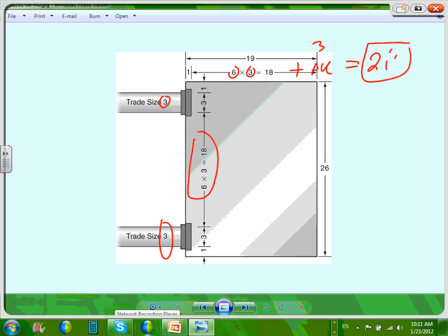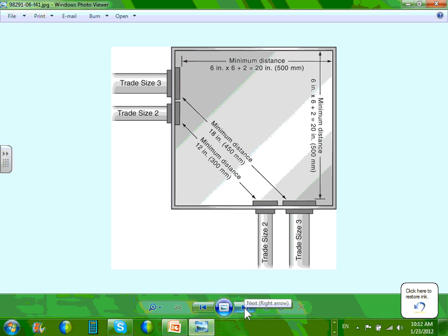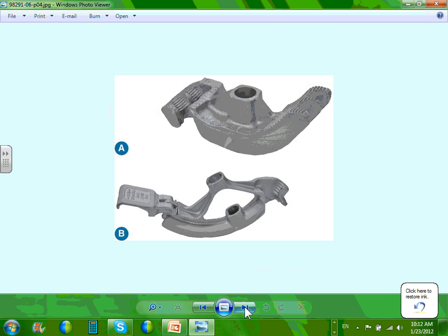Any comments, guys, about the pull box? We're not using a pull box in this project, but really pay attention to the 6 times the largest conduit if it's a U or angle pull, and 8 times the largest conduit if it's a straight pull. And there are a couple of good examples that we have. This is the distance between them, and I'm going to move on into the threaded.